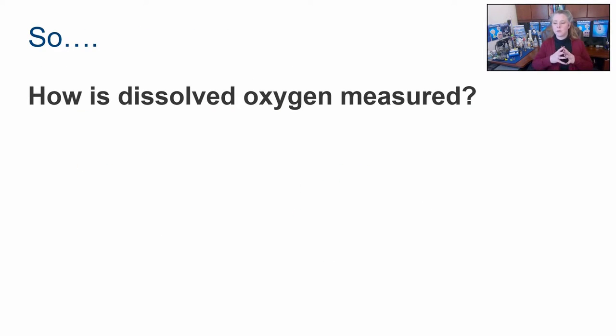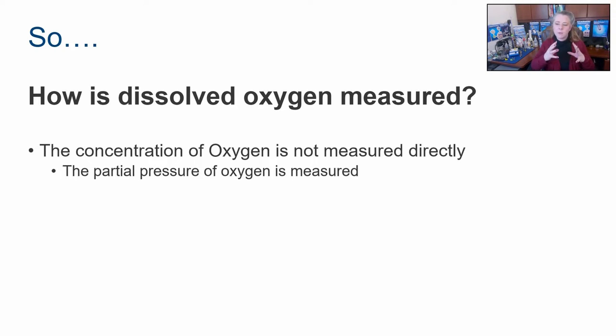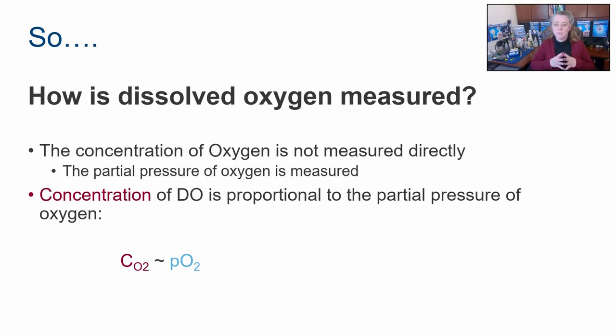So the most important thing ever is, how do we measure dissolved oxygen? Well, that's a funny thing. It's considered a critical process parameter, but we don't actually measure oxygen directly. Instead, what we measure is the partial pressure of oxygen. If you remember way back when, to dissolved gas laws, we think about partial pressures. And what we find is that the concentration of dissolved oxygen is actually proportional to the partial pressure of oxygen.